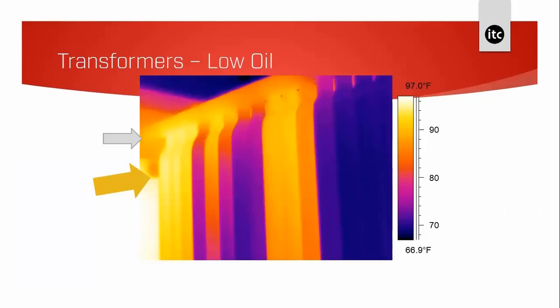Low oil in a substation: the fill level of these units is crucial for cooling — the oil expands and flows into the radiator tubes to release warmth to the environment. We can quite clearly see in this image several different levels of cooling happening, indicating that oil level is causing the issue.